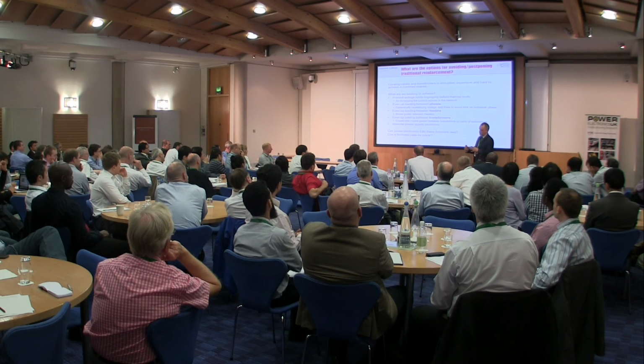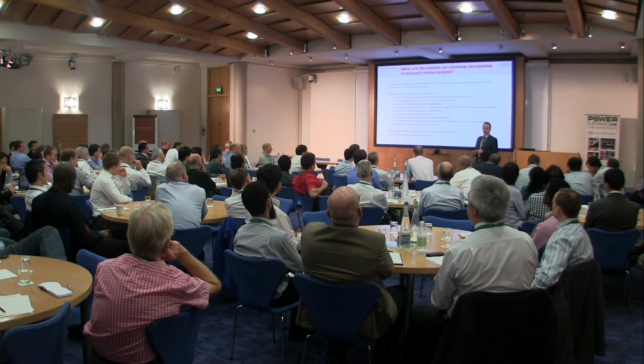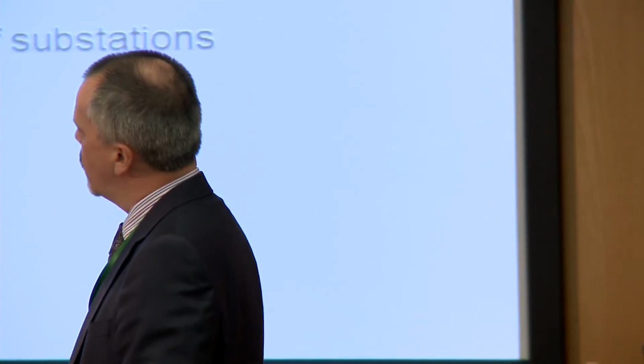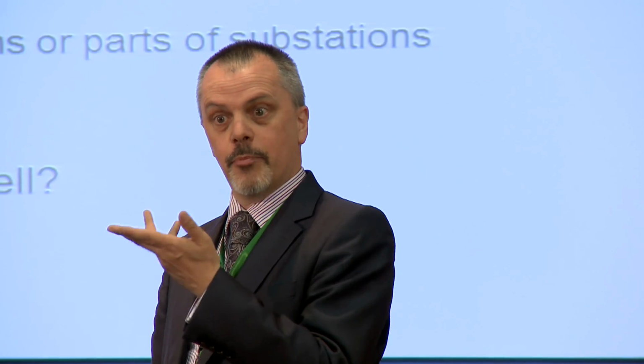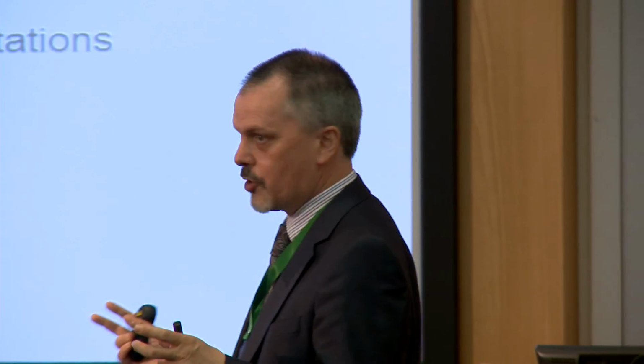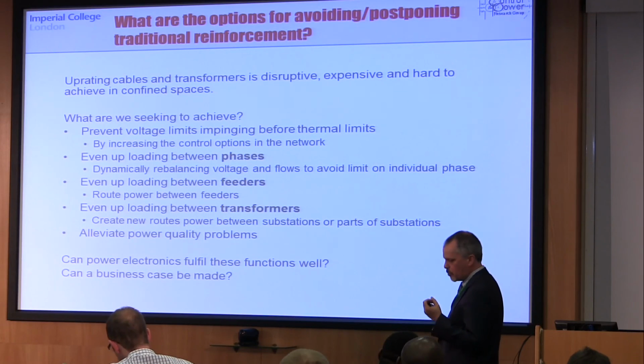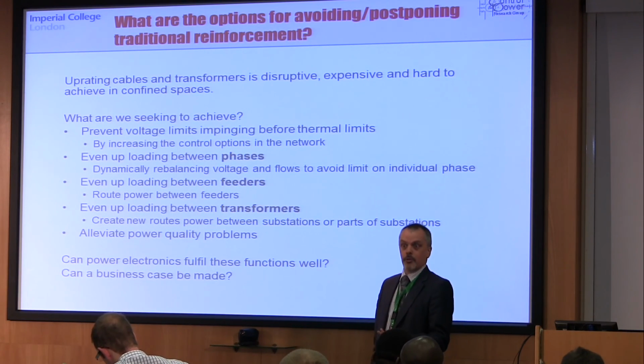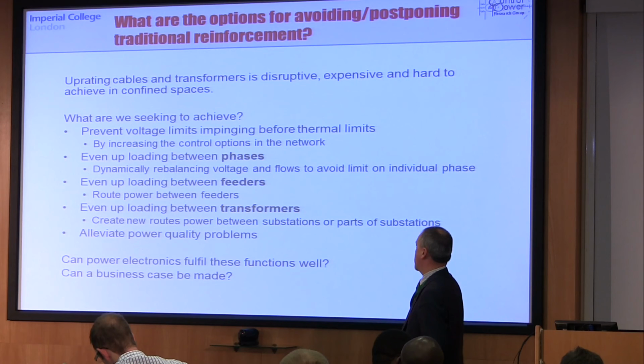On many suburban feeder systems, voltages start hitting the lower or upper limit long before you hit the thermal limit of the feeder's current-carrying capacity. It's to do with the load density on those feeders, and better voltage control is something we could potentially achieve with power electronics.